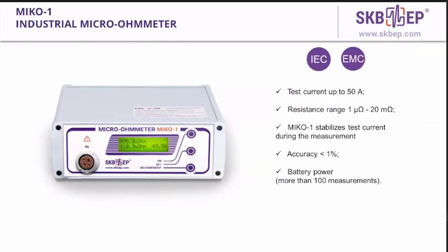The next we have is MIKO-1. We call it an industrial micro-ohmmeter. It's one of our common instruments in the range of instruments we produce. This device is very easy to use and very simple. It only has 3 buttons. It has built-in battery power for more than 100 measurements, and it has a test current of up to 50 ampere.